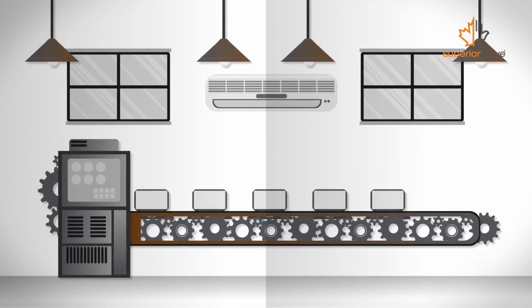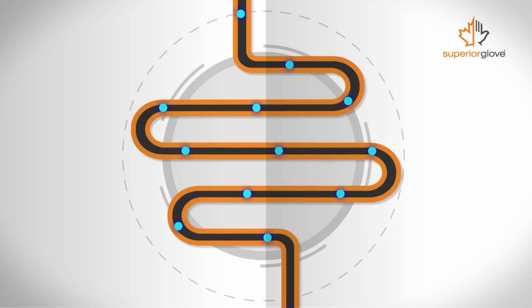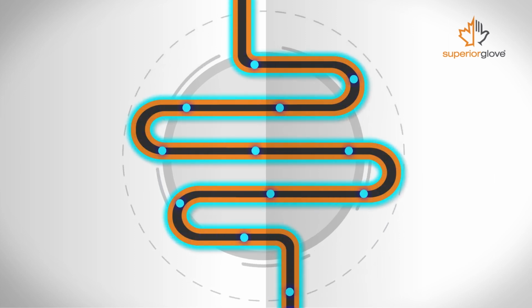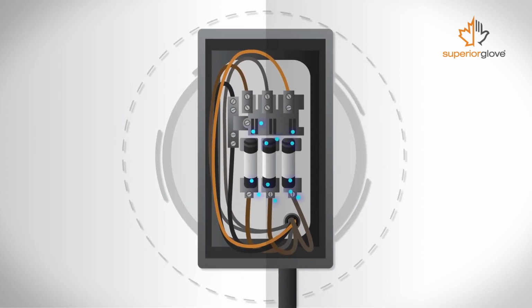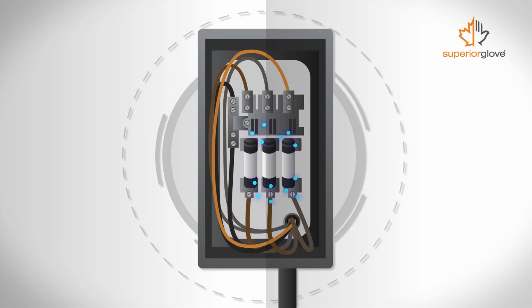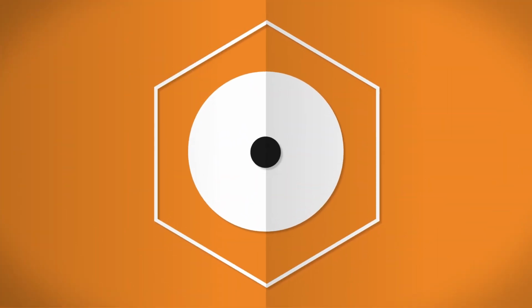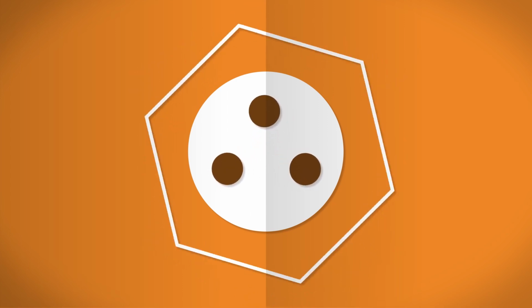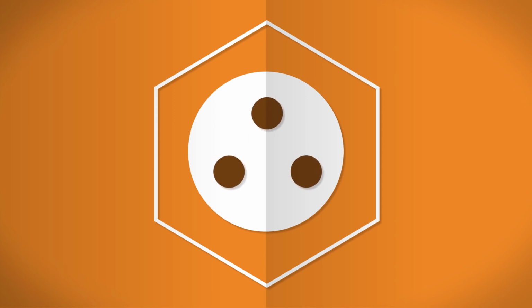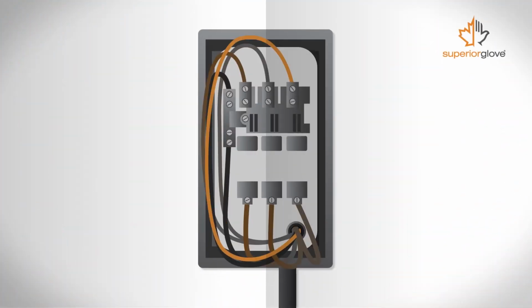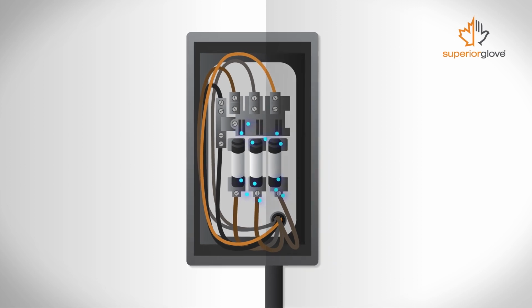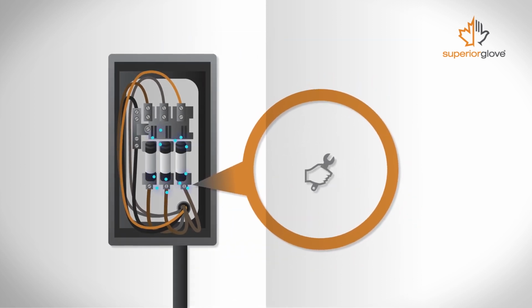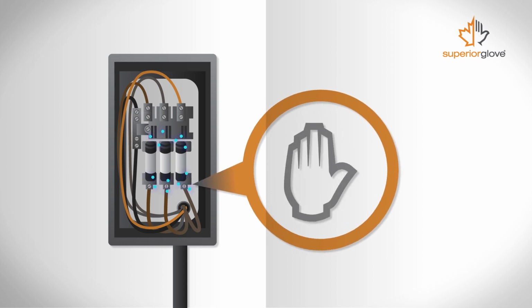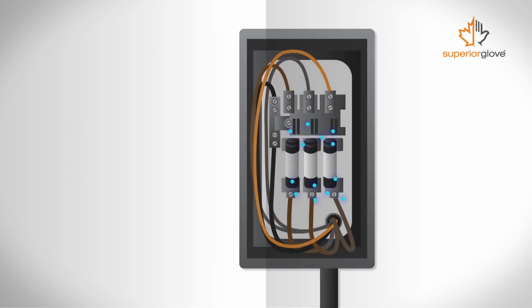When electrons move back and forth across a conductor, like a wire, a small area outside of that conductor is energized. Voltage can push those electrons off the conductive surface and onto atoms and molecules in the air. These atoms become ions because they have an electric charge. The air that is around us is a pretty good insulator to stop these ions from causing an explosion, but it's not perfect. If another conductor gets inside that energized area, a wrench, moisture in the air, dust buildup, or someone's hand, the electrons will travel through that new path.